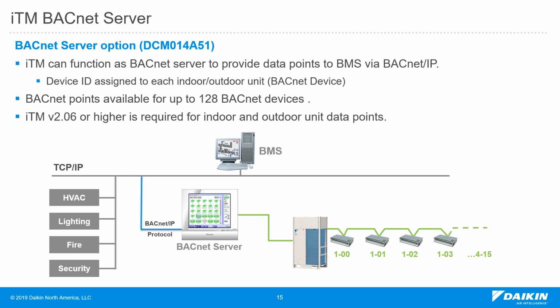So every indoor unit or every outdoor unit will act as a device. Every outdoor unit system will act as one device. After that, the points will show up in the BACnet network under each device. And we also teach in the ITM BACnet commissioning class how to commission the BACnet server and how to provide the outdoor unit data to the BMS integrator.